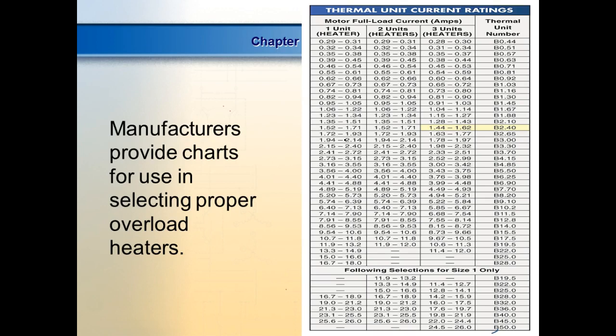So probably it's going to be the equivalent horsepower. I mean, watts per horsepower? 746. It's actually 745.7, I think. Most of it is 746 watts per horsepower. So there's not going to be enough difference. You're going to have to know the difference with kilowatts because you'll run into these different motors out there, depending on what company you go to work with, whether it's rated in horsepower or in kilowatts. Now, I prefer kilowatts because it gives you a good indication of what your full load current is in amps.